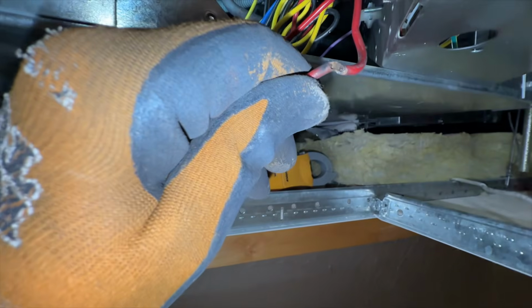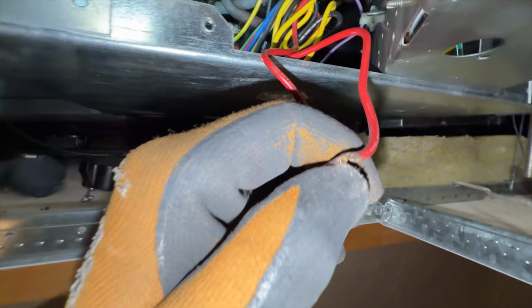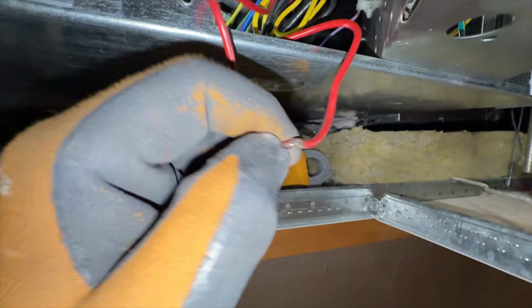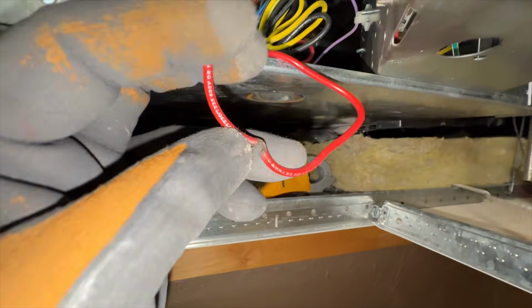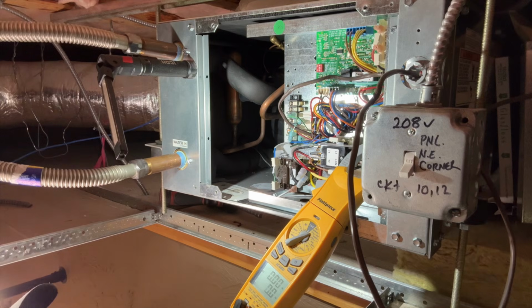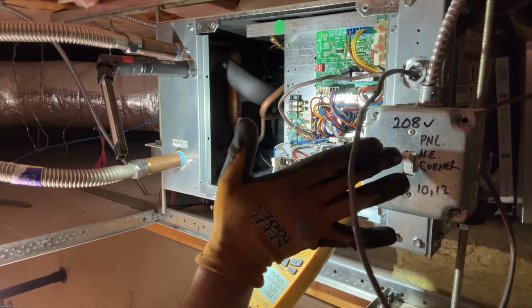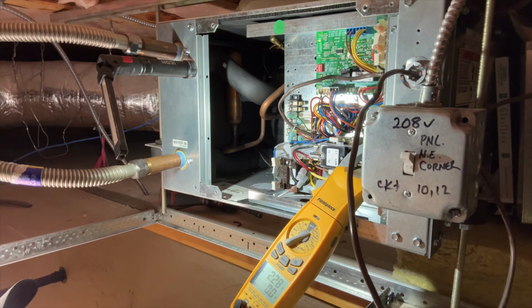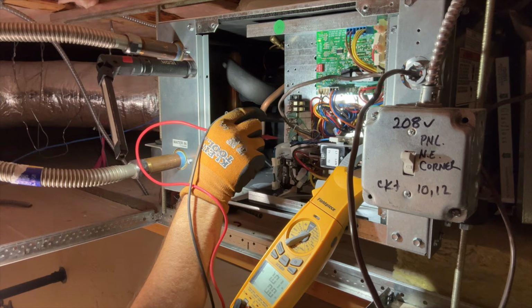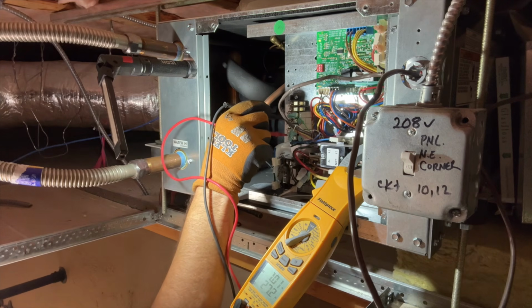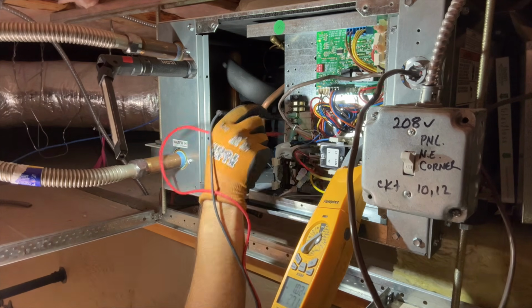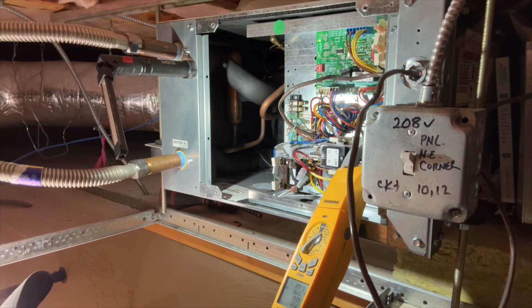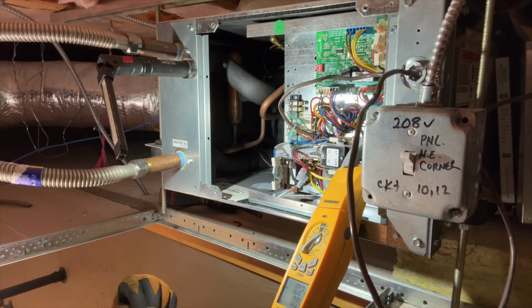All right, I found the damage here. As you can see here, I think it was pinched behind this panel, and when it would vibrate just right, it would short and pop the breaker. So we need to repair that. Oh man, cool. So let's fix this, and then we should be good to go. Okay, moment of truth. Turning on the power. Blower kicked on. Let's see if we actually get 24 or 27 volts now. We should, because I changed the thing. Yep, 27.2 volts, much better. All right, so we just gotta wait till the compressor kicks on and hopefully it doesn't blow up.